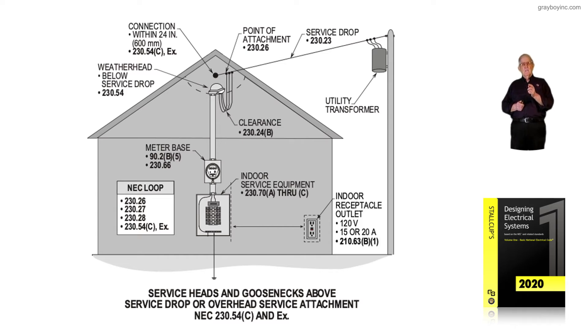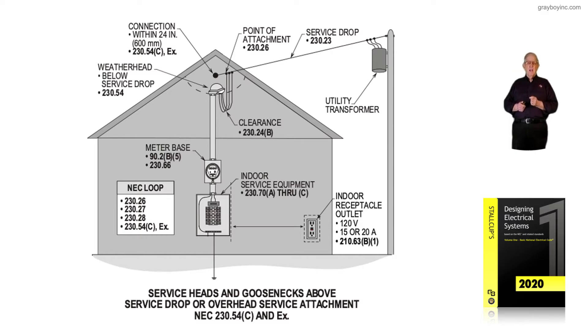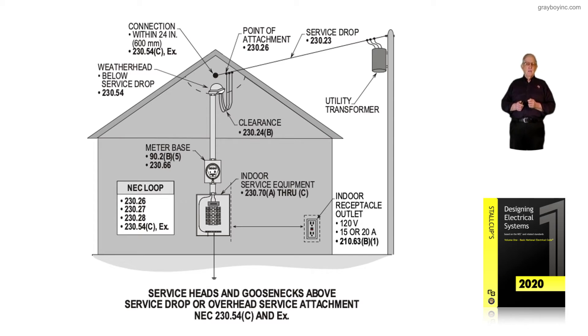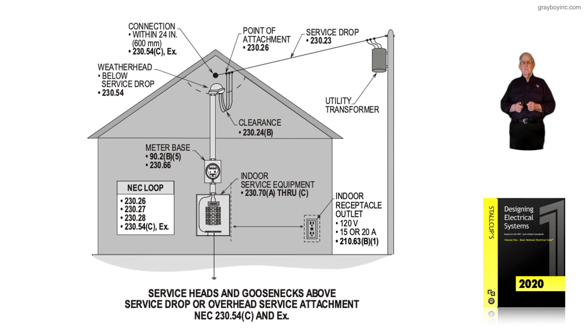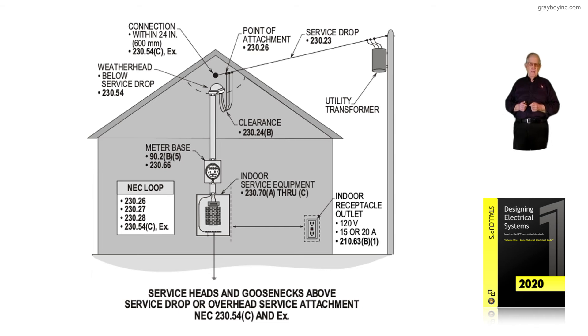A lot of times you'll see it 24 inches to the right, to the left, or above the attachment point, in accordance with the authority having jurisdiction. Notice we may have a receptacle located outside within 25 feet that's GFCI protected. NEC 210.63B1 now says if the panelboard is indoors, we have to have the receptacle; if it's outdoors, it doesn't call for it.